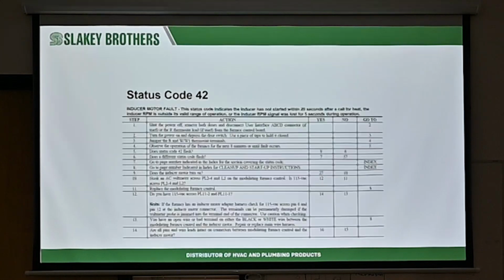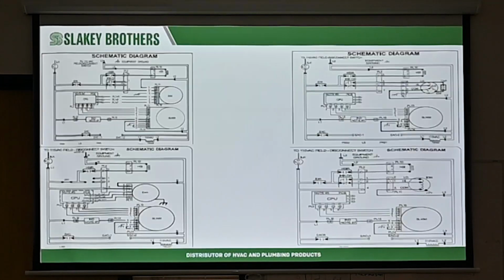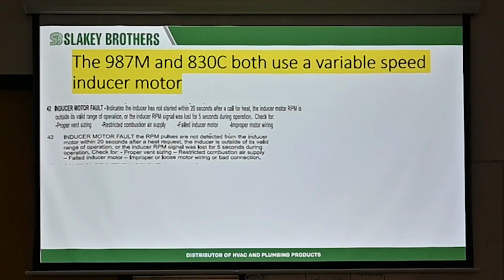Again, I use the same blower motor, same inducer motor. I haven't had a single blower motor or a single inducer motor, and I hope it doesn't bite me here, but on fresh startup, I have not had a single one of those ever be bad out of the box on a 987. So for you guys doing an installation, generally it's just going to work. If you have a fault where it says it's a blower motor fault, something wrong with the blower motor, it doesn't want to kick on, always check all your plugs. Sometimes things just aren't plugged in all the way. That is like 99% of the time on a brand new install usually the issue.